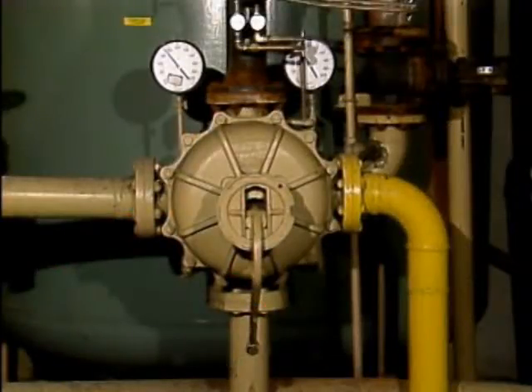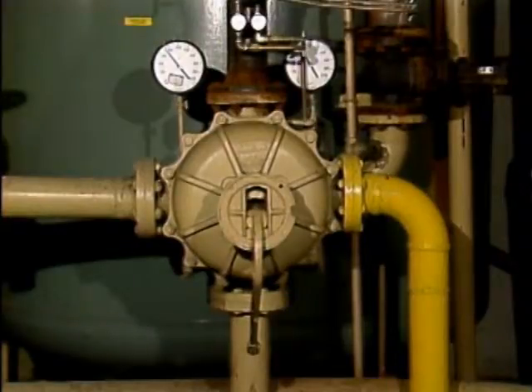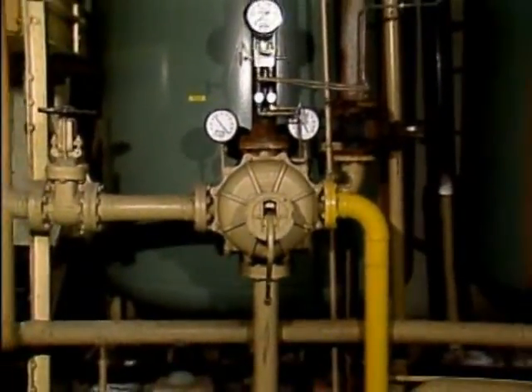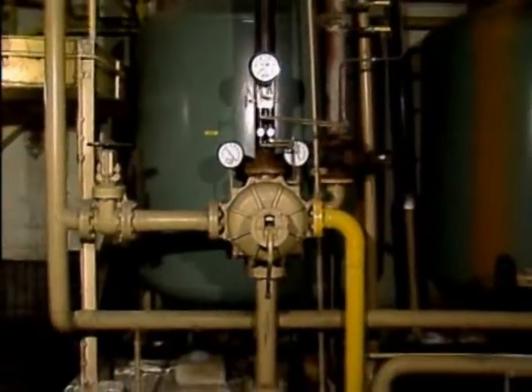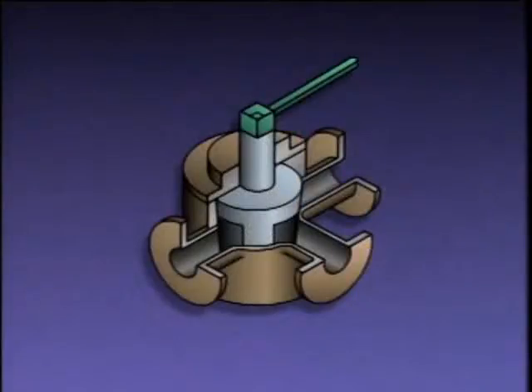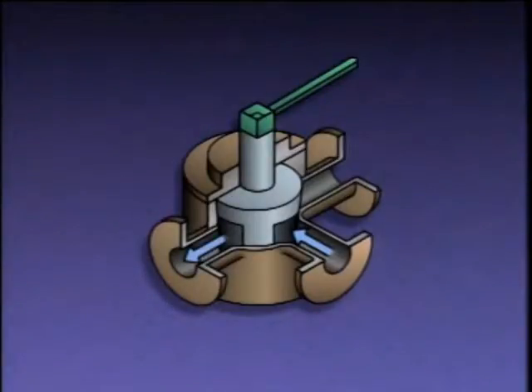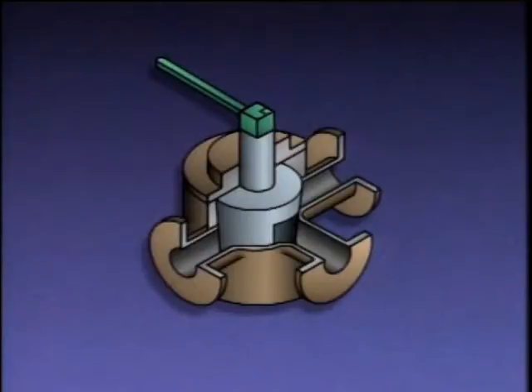Another type is the multi-port plug valve, which has additional piping connections and a different type of plug. Instead of an opening that allows fluid to pass straight through, a multi-port plug has an L-shaped opening. In a three-way multi-port plug valve, rotating the plug to different positions changes which inlet and outlet ports are connected, directing fluid flow accordingly.